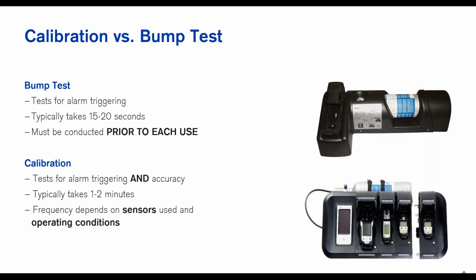And so if I have a cylinder of calibration gas that's got 25 parts per million of CO, 100% of the LEL, whatever it is on the label of my cylinder, it should be matching it up when I expose that to my meter. And so if the calibration gas cylinder is supposed to be showing 25 parts per million of CO, and then when I expose it to my meter it's reading 50, then there's an issue there. And so this calibration is going to correct that issue. Most of the time it does, I should say. Sometimes it doesn't. Sometimes there's an issue with the meter itself. Maybe there's a failed sensor, there's something wrong with the internal circuitry. But a lot of times this will fix that and correct that.